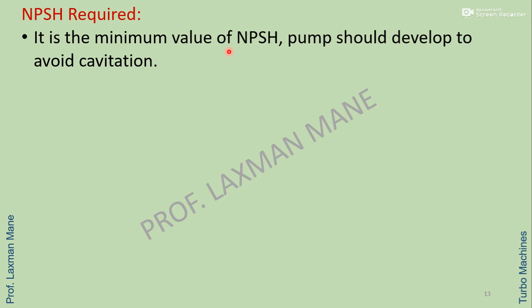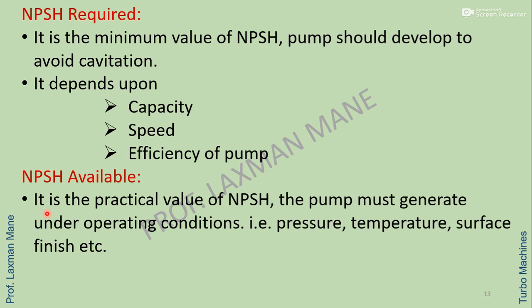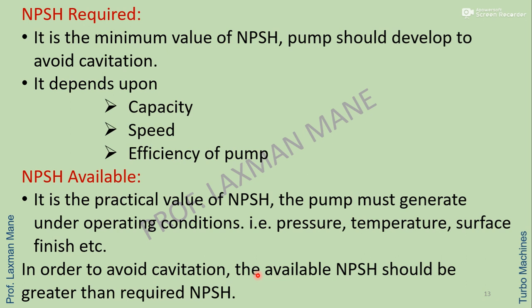NPSH required is the minimum value of NPSH that the pump should develop to avoid cavitation. It depends upon the capacity, speed, and efficiency of the pump. NPSH available is the practical value of NPSH the pump must generate under operating conditions, i.e. pressure, temperature, surface finish, etc. In order to avoid cavitation, the available NPSH should be greater than the required NPSH.